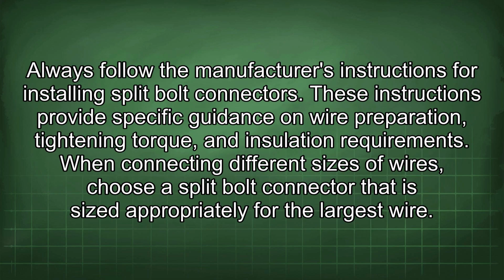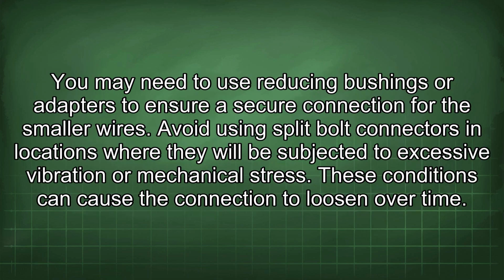Always follow the manufacturer's instructions for installing split bolt connectors. These instructions provide specific guidance on wire preparation, tightening torque, and insulation requirements. When connecting different sizes of wires, choose a split bolt connector that is sized appropriately for the largest wire. You may need to use reducing bushings or adapters to ensure a secure connection for the smaller wires. Avoid using split bolt connectors in locations where they will be subjected to excessive vibration or mechanical stress. These conditions can cause the connection to loosen over time.